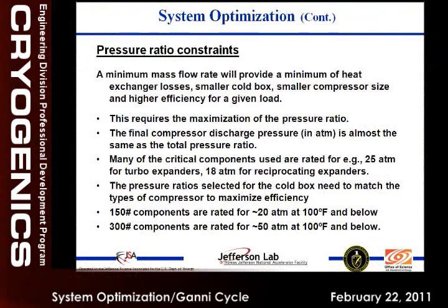Like I was implying at the beginning, how do you set the pressure ratio? If we increase the pressure ratio, we know we can pack more availability on the high side. But it comes with some kind of reliability cost, because if we keep pushing the pressure up, a lot of components which rotate, which turn, and the seals cannot take the differential pressure between the high pressure and the eventual seal of the environment. As the differential pressure increases, they will start developing more leaks. So sooner or later, you will start getting into reliability issues if you keep pushing the pressure ratio up.